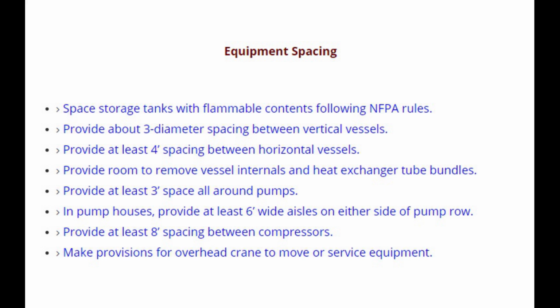Number 5. Provide at least 3 feet space all around pumps. Number 6. In pump houses, provide at least 6 feet wide aisles on either side of pump row. Number 7. Provide at least 8 feet spacing between compressors. Number 8. Make provisions for overhead crane to move or service equipment.